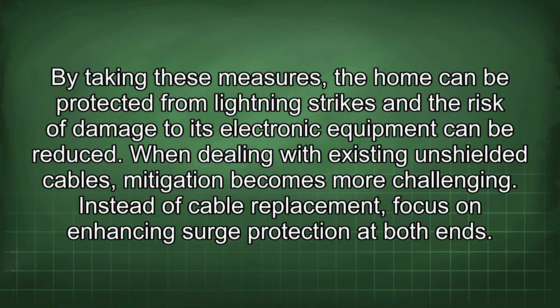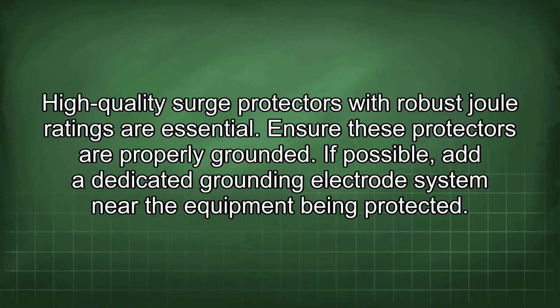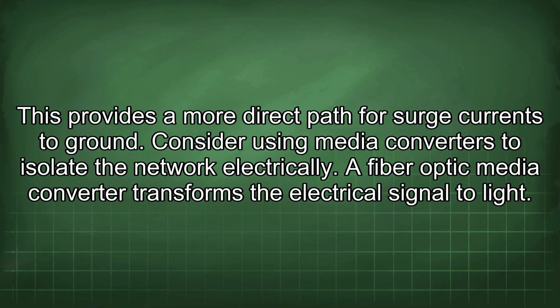Instead of cable replacement, focus on enhancing surge protection at both ends. High-quality surge protectors with robust Joule ratings are essential. Ensure these protectors are properly grounded. If possible, add a dedicated grounding electrode system near the equipment being protected. This provides a more direct path for surge currents to ground.